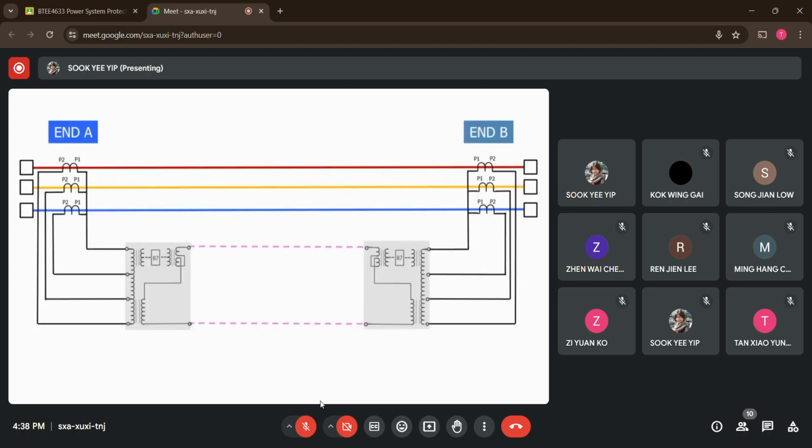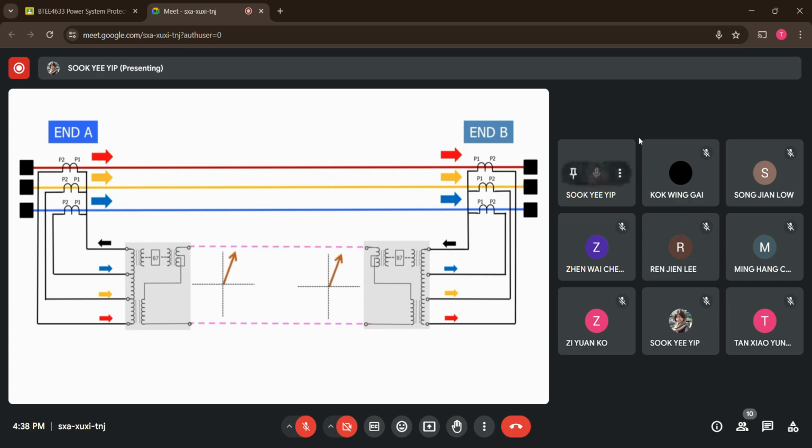When the feeder is energized, the single-phase voltage phasor generated by the summation transformer will be the same at both ends if the three-phase currents are the same. The way that this information is used will depend on the design and manufacturer of the differential feeder protection relay. Some relays will measure the current that flows down the pilots when there's a difference between the single-phase voltage vectors.